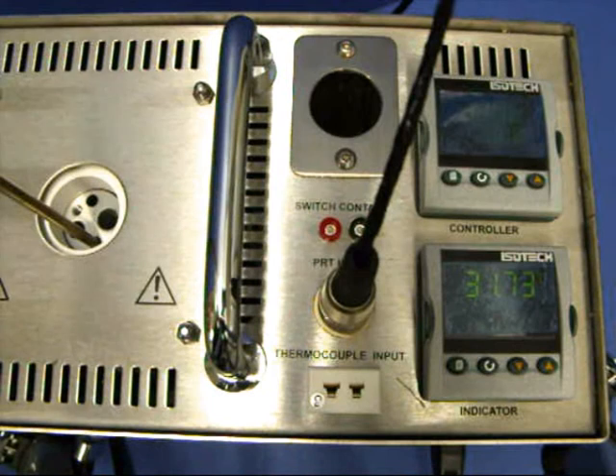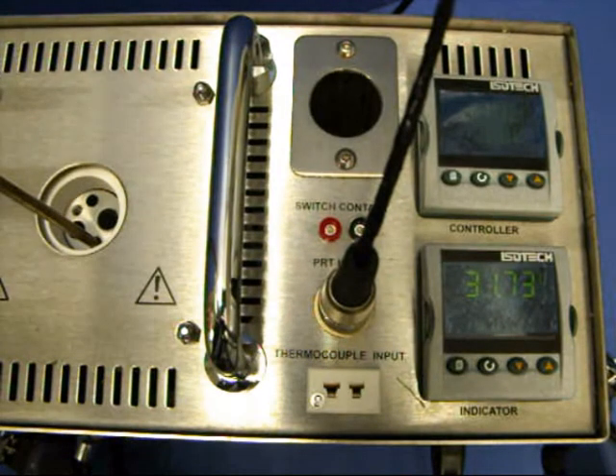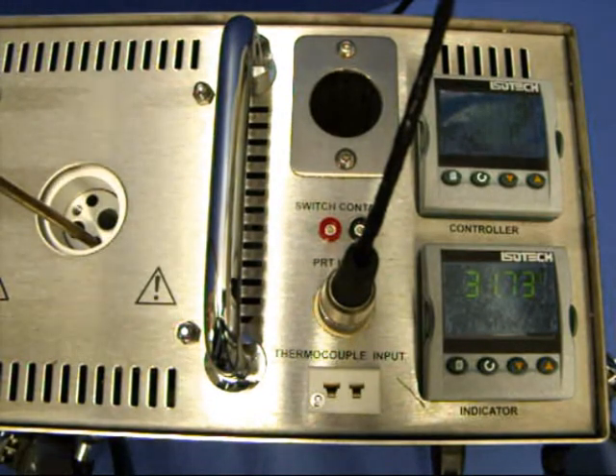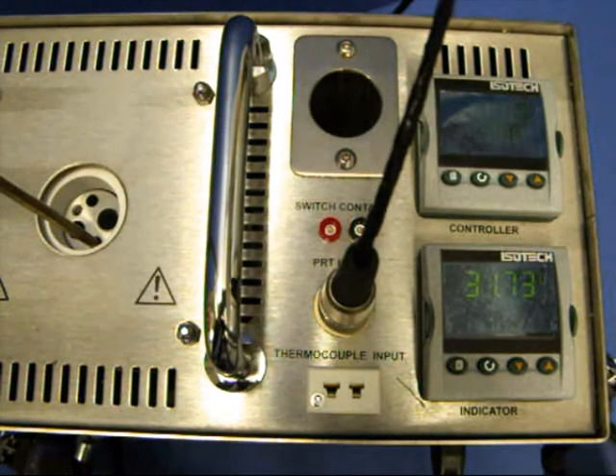When the custom or user calibration is active the indicator will show the REM beacon lit continuously. The use of user calibration can make a significant difference to the accuracy of the instrument and this REM beacon provides a clear and continuous indication of the calibration status.